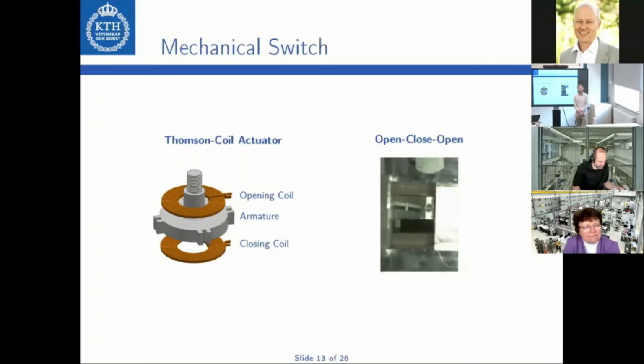The coil is actually relatively small and the current pulse is very high. In the experiments we ran, the current pulses were about 15 kiloamps, that kind of magnitude, but the current pulse itself only lasts 500 microseconds. That's why the coil is not heated up substantially, and that's why it does not need a cooling system. Also, the actuator is only operated when the DC circuit breaker operates, which should only occur in a fault case or for rare switching events, so there are no losses that heat it up all the time. That's why I think this cooling system does not have to be included.